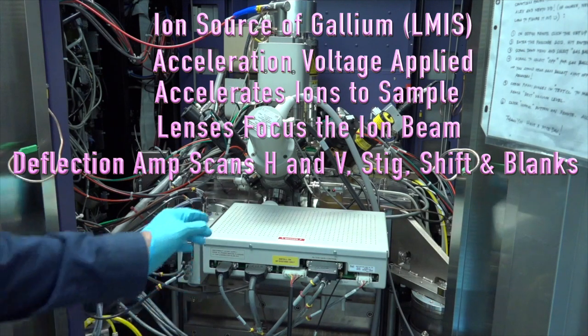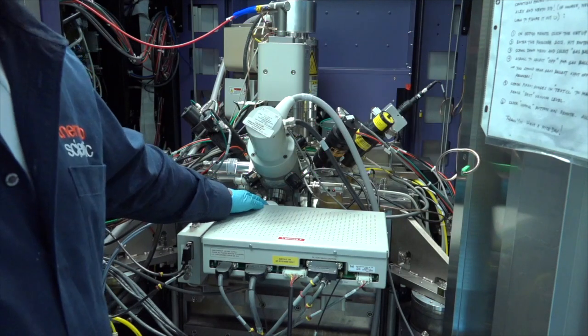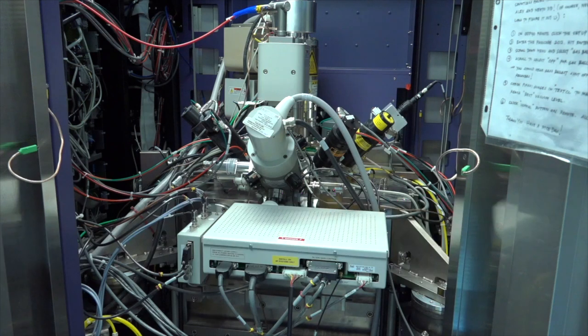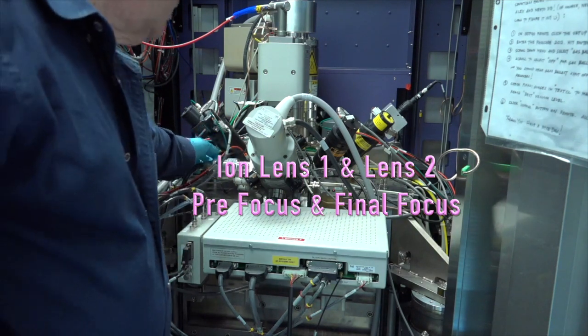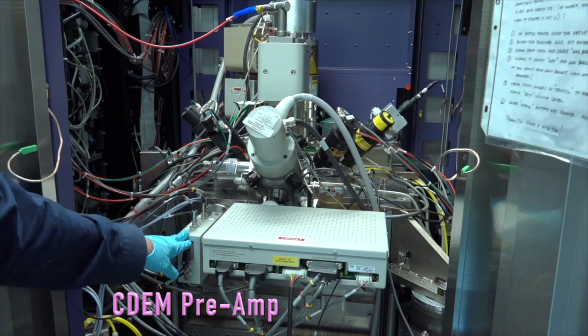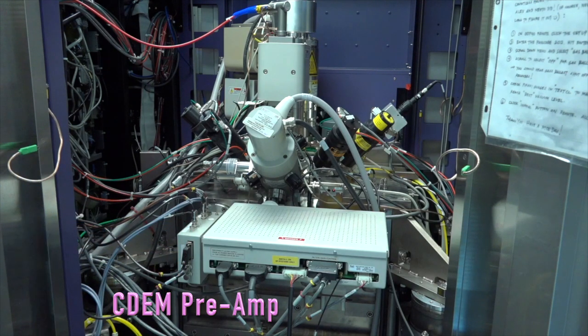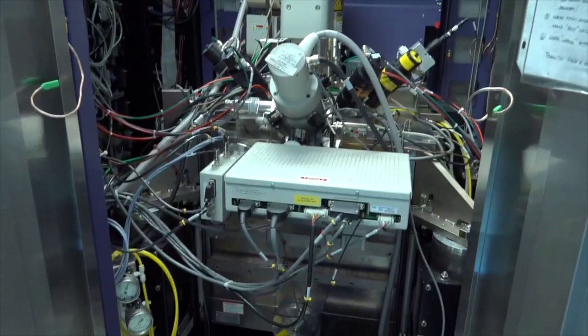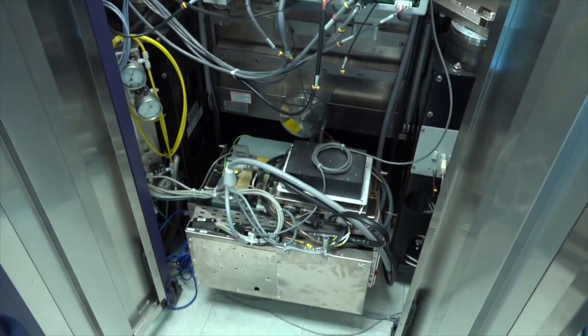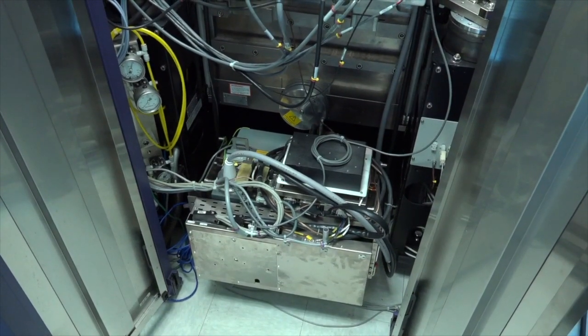On here we also have — you can just barely see the top of it here — the ABA controller: Automatic Variable Aperture strip controller. Exactly like the one for the E column, but the apertures are different sizes. Lens one is here and lens two is just below it for pre-focus and focus of the beam. And right over here you can see a CDEM detector — we'll talk about it a little bit. Below this whole level, I can show you the tank that develops the voltage for the ion column. You can see right here it's got an HTSU — the high tension supply unit — for the ion column.